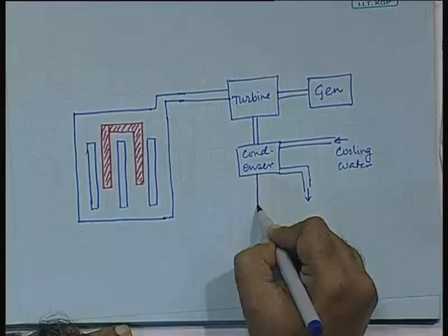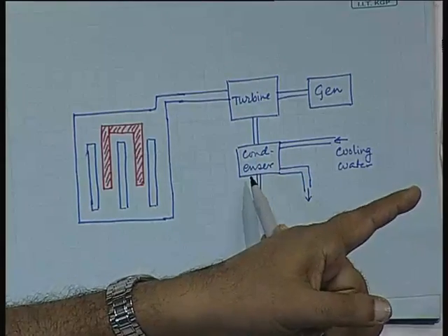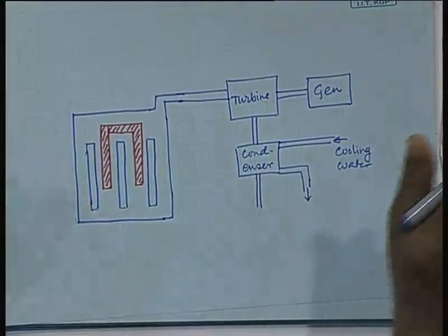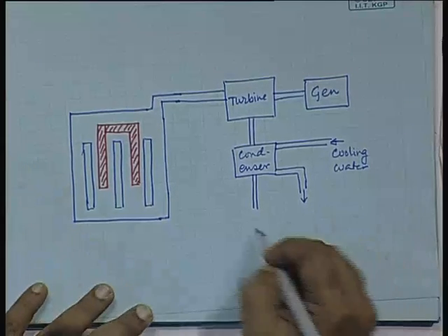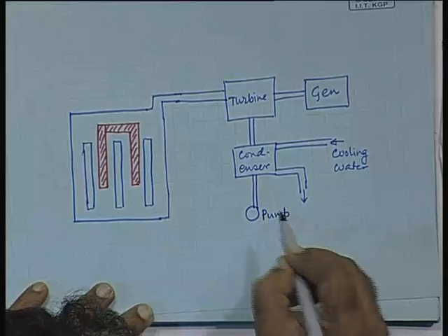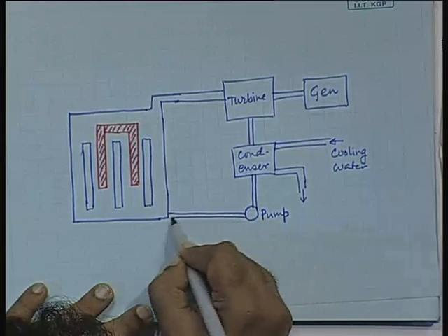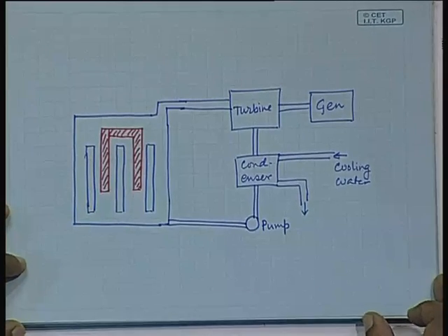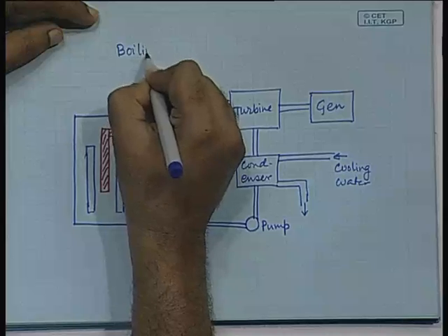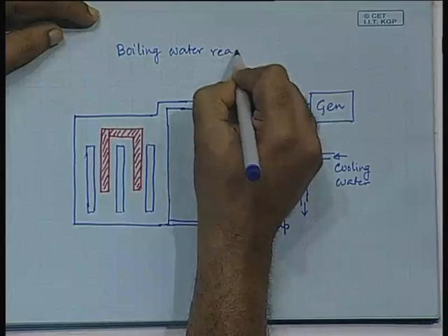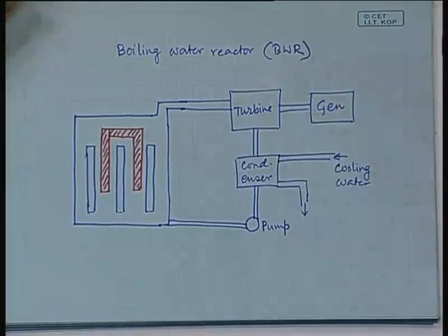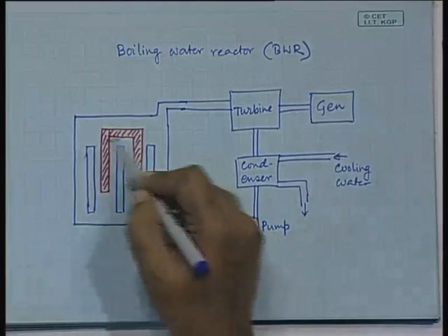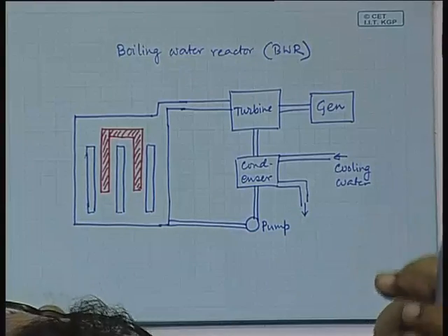Okay. Then after that, what will you have? After turbine and condenser, what will you have? Remember, it also works on the same fuel cycle. No. After condenser, it has become water. It has to go to the pump. Yes, it goes to the pump, and pumped water must go into this. So, that is the essential structure of what is known as the boiling water reactor. Where you hear about the abbreviation BWR, it is nothing but boiling water reactor, because inside the chamber it actually boils.